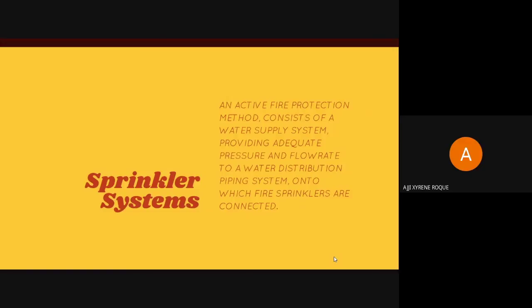Ang common conception ng ibang tao sa sprinkler system, ang dinedetect nito ay yung smoke. Mali ito. Fire sprinklers are not triggered by smoke, they are heat activated. It is an easy mistake to make since heat is carried upward with smoke from a fire. As heat intensity increases, the sprinkler sensing elements become exposed to elevated temperatures and begin to deform. Most sprinkler heads feature a glass bulb filled with glycerin-based liquid that expands when in contact with high temperature. When the liquid expands, it shatters the glass and the sprinkler head activates. When heat hits a sprinkler head, a valve opens, discharging water onto fire and beginning the suppression action.